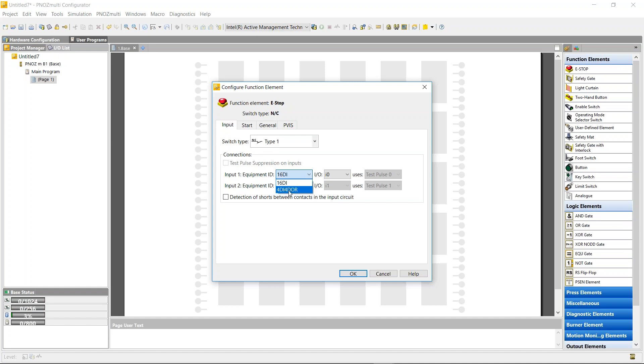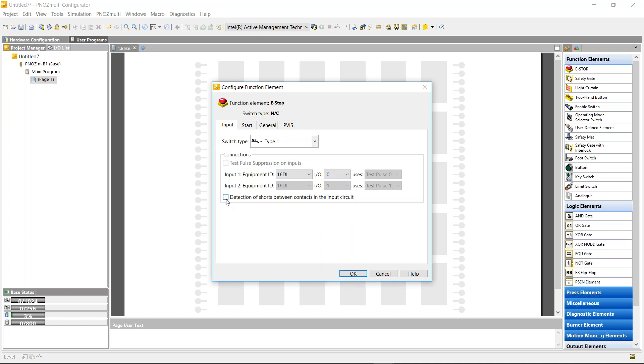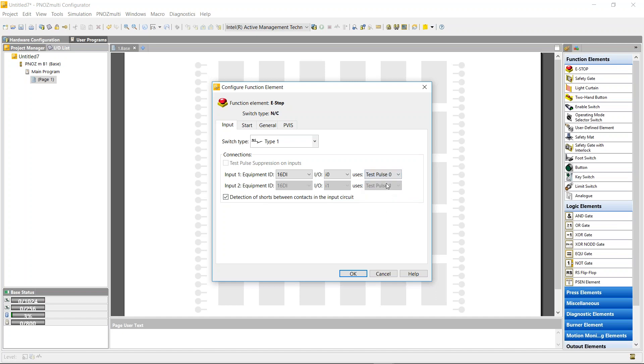It asks me the location where I want to put it. I want to put it in the module with 16 digital inputs at i0. I'm going to use detection of shorts and I'm going to use test pulses. I've got four test pulses on the base unit and I'm going to assign test pulse zero. So the e-stop is going to be run via test pulse zero through the e-stop and back into i0.